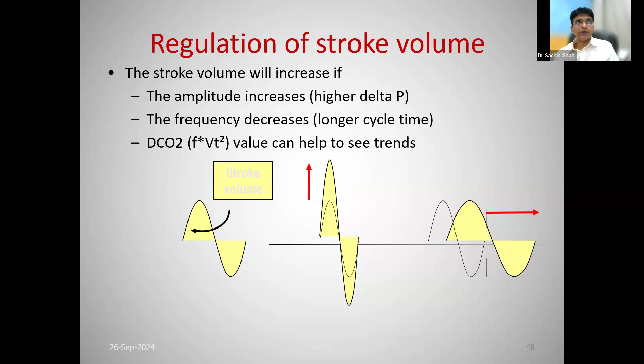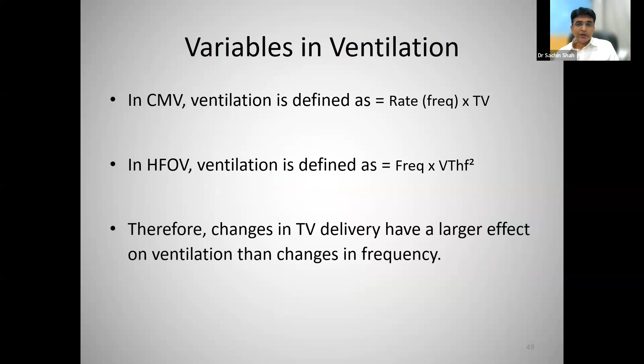Carbon dioxide levels are a correlation of the tidal volume. And now there are newer machines which monitor the tidal volumes, so we'll talk about that. You get the value of DCO2, which is the coefficient of carbon dioxide. It is frequency multiplied by tidal volume squared. In conventional ventilation, minute ventilation is rate times tidal volume, but in HFO, it is frequency times tidal volume squared. So even a smaller change in the tidal volume will lead to a significant change in the carbon dioxide levels.